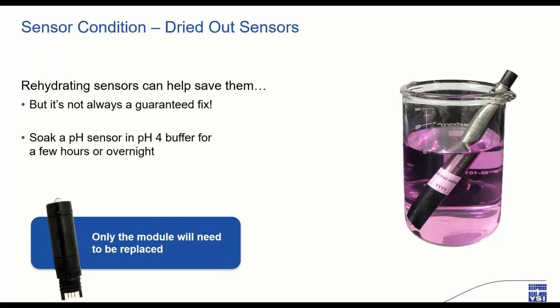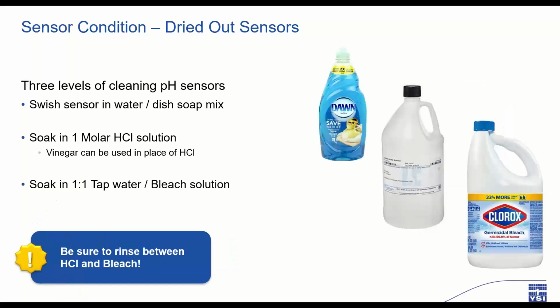Before I toss a pH electrode, however, there's another step that might be worth a shot. There are 3 levels of cleaning that can be done to a pH electrode. The first is very simple. Place a couple drops of Dawn dish soap in a plastic beaker of warm water and vigorously swish the sensor around to clean off any light debris that might be interfering with calibration.